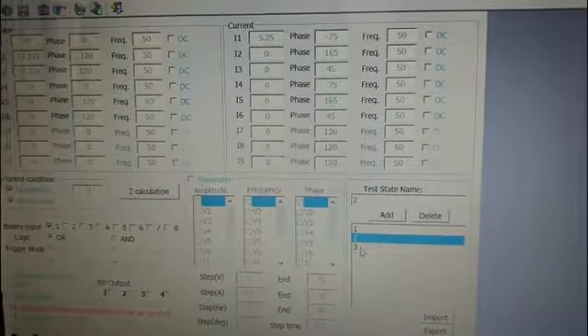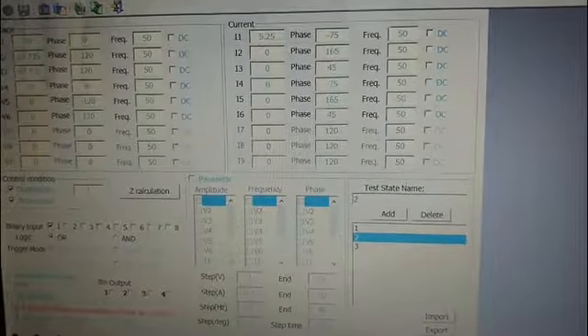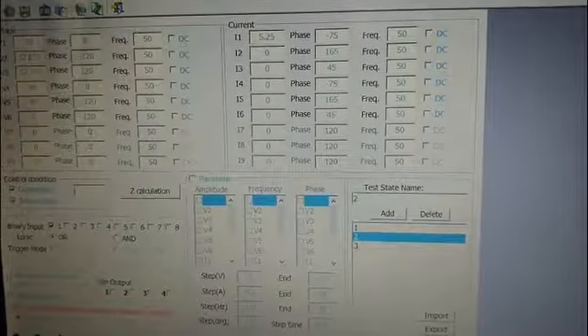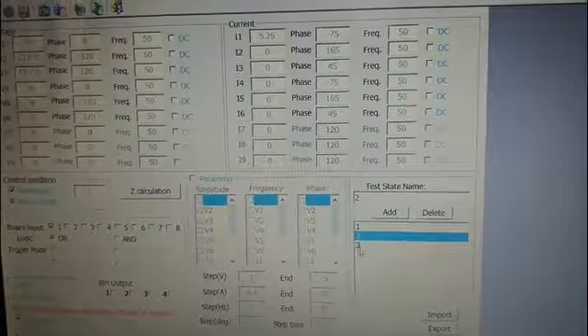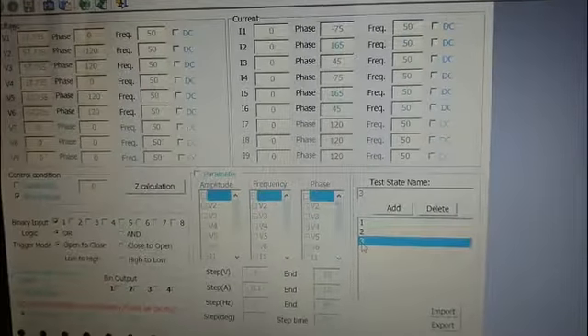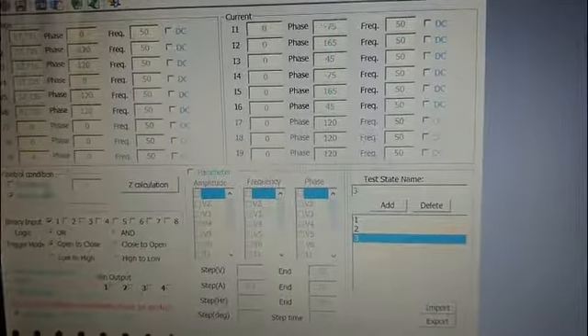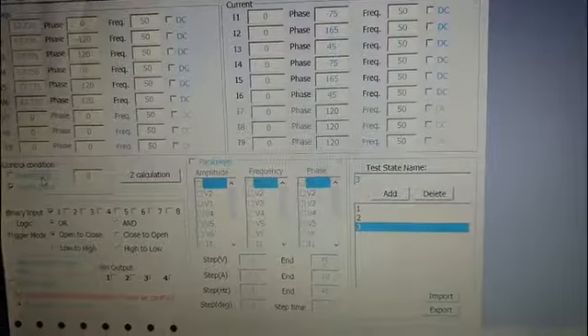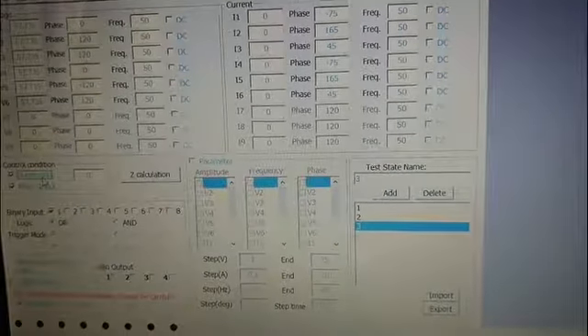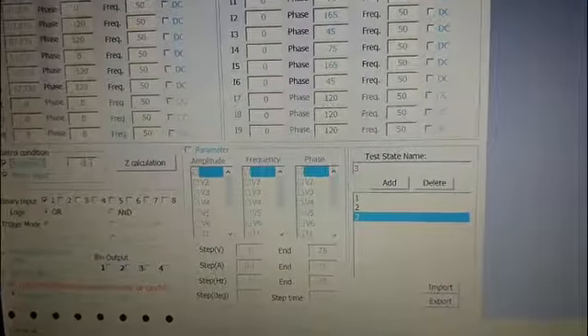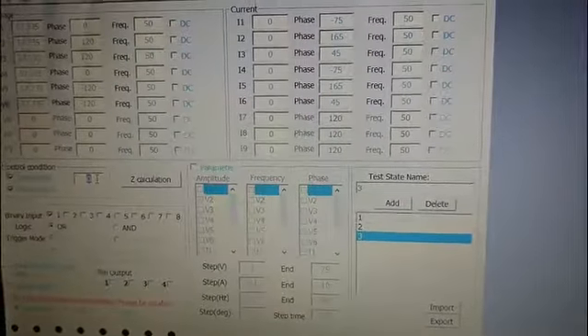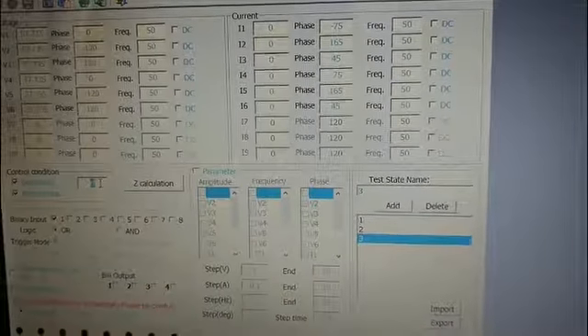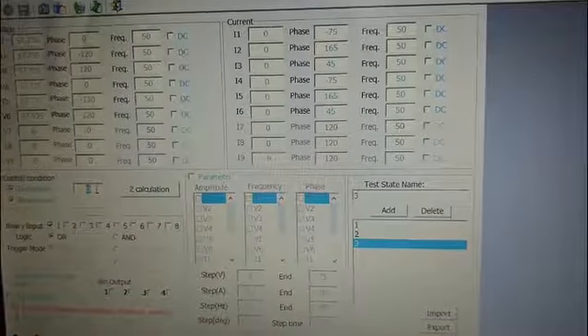Next is the reclosing situation. The setting time of reclosing is 1.2 seconds. We input the duration 2 seconds and choose binary input.